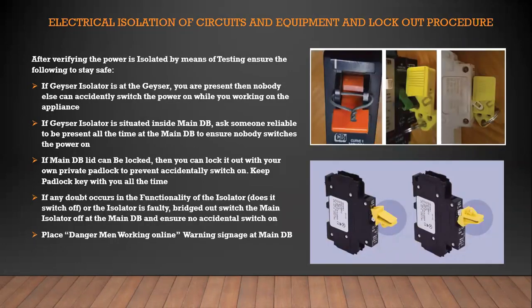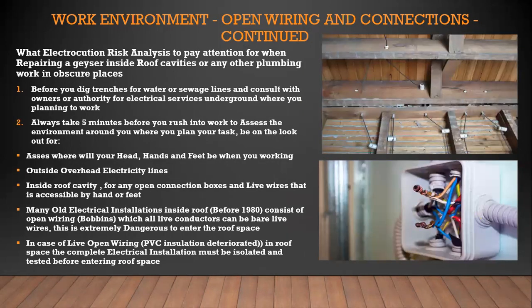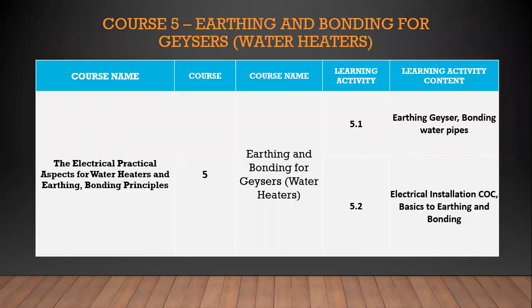I also address isolation equipment, how to lock out circuit breakers. If there's no lockout means, what else to do: put somebody there to switch the main power off, put a person at the DB while you're up in the roof to ensure that nobody switches the power on. We're looking at the work environment. Inside your work environment, especially in the roof spaces, you'll see there's photos of open wiring. You will find open junction boxes or termination connection boxes in roofs, which can be very dangerous because wires could be open against the regulations and there's live power there, and that could be fatal. So we've addressed all those safety aspects in this course 4.